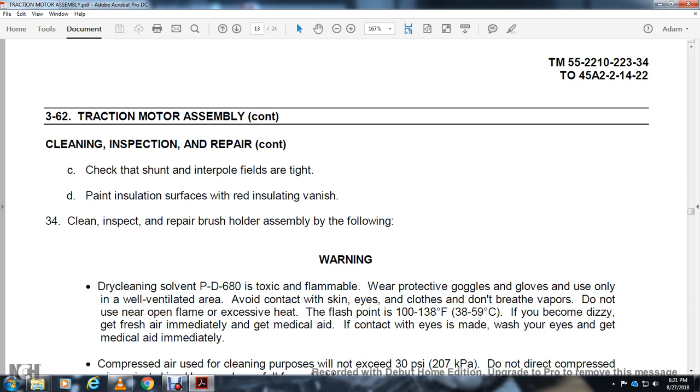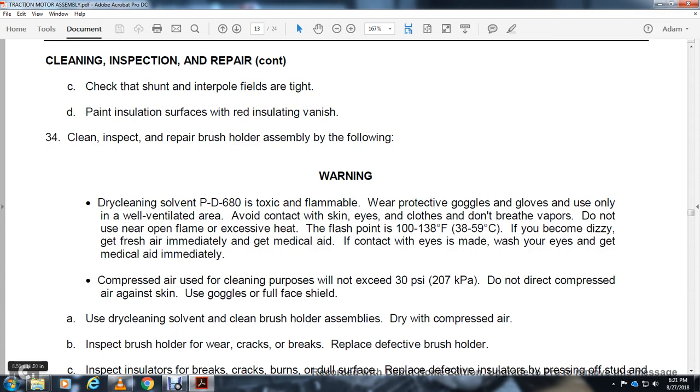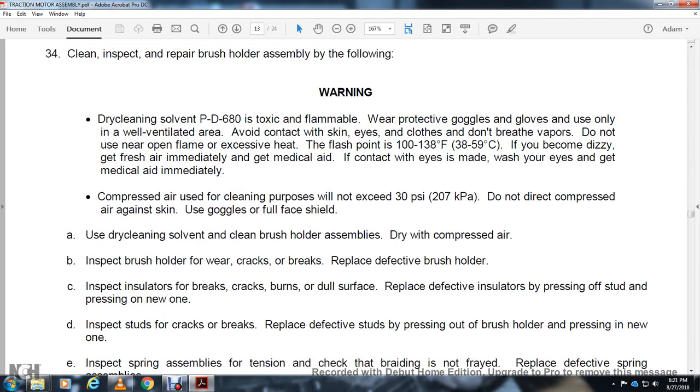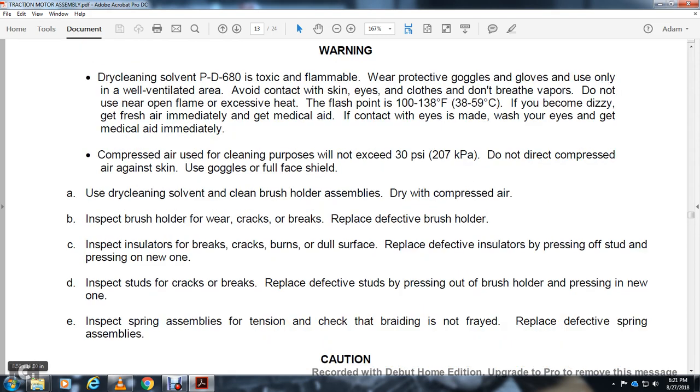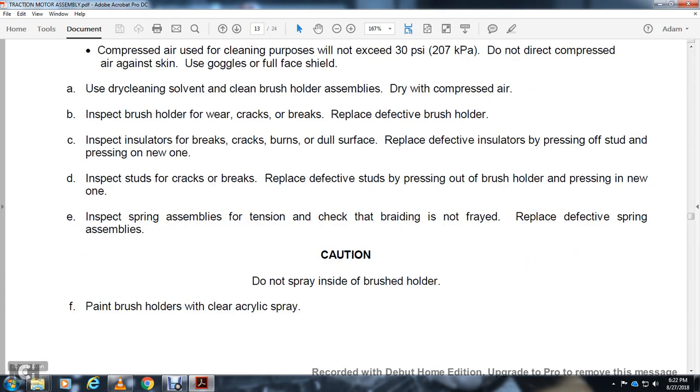Check and inspect — repair brush holder assembly. Warning — dry cleaning solvent PD-680: flammable, wear protective gloves. Use only in a well-ventilated area. Avoid contact with skin and eyes. Do not breathe vapors. Do not use near open flame. Flash point 100–138 degrees Fahrenheit. If dizzy, get fresh air and medical aid immediately. Compressed air for cleaning: limit to 30 PSI. Do not direct compressed air against skin; use full face shield. Use dry cleaning solvent and clean brush holder assembly, then dry with compressed air. Inspect brush holder for wear, cracks, and breaks; replace defective brush holders. Inspect insulators for cracks, burns, and surface damage; replace defective insulators. Inspect studs for cracks and breaks; replace defective studs by pressing out old one and pressing in new one. Inspect springs for proper tension and check braiding; replace defective springs. Caution: do not spray inside of the brush holder and paint with clear acrylic spray.